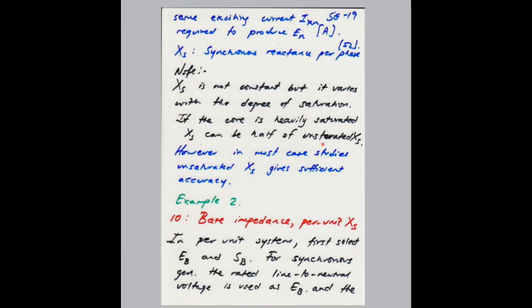So we will look at examples of how we can determine those two values. One is the unsaturated synchronous reactance and one is the saturated reactance. We will look at that in one tutorial question, where we will look at a machine that's connected to a utility grid, and we will look at the open circuit characteristic and the short circuit characteristic of the machine. We will use those characteristics to determine the saturated and the unsaturated value of the synchronous reactance.